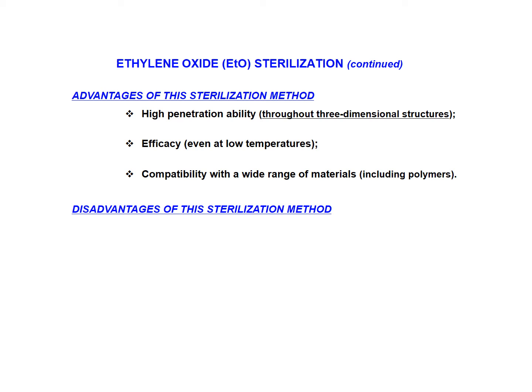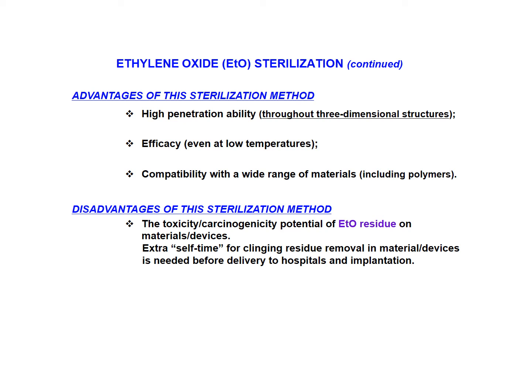The sterilization method of ethylene oxide, however, has certain disadvantages. First and foremost is the fact that this particular gas is toxic and potentially causes cancer. This can be the result of even a few residue molecules of the gas on materials and devices. This residue remains clinging on the surfaces of the materials and devices even after the process of sterilization is completed. For this reason, extra self-time is needed to effectively remove the clinging residue before the materials and devices are delivered to hospitals and implanted.